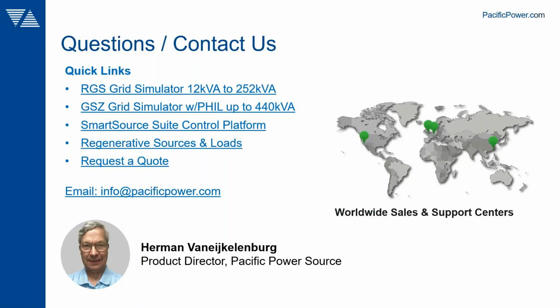How many GSZ systems can you parallel? Typically up to about 8. We could consider going a little higher, but we'd want to do some additional testing. It has to do with the number of units that can be connected together in terms of system interface, load capability, and distance. So 8 for sure, possibly a few more. That's about 440 to 500 kilowatts right now. We can work with customers if you have specific requirements for that.